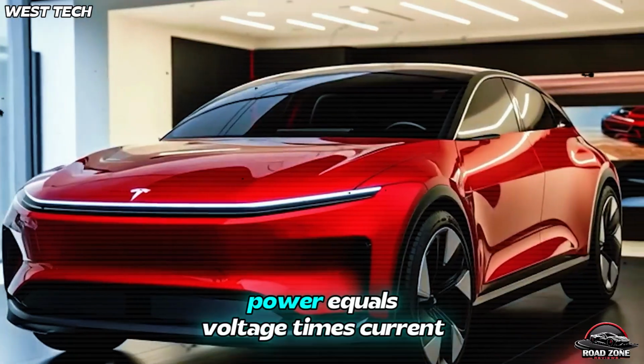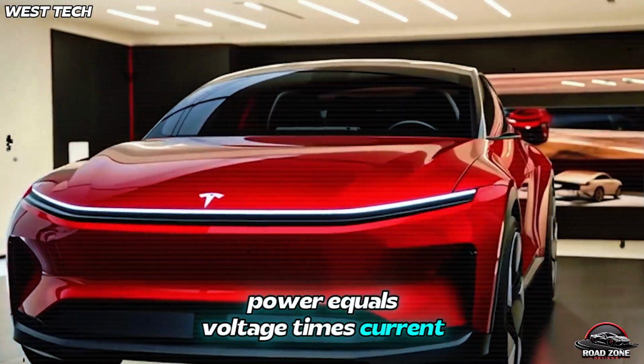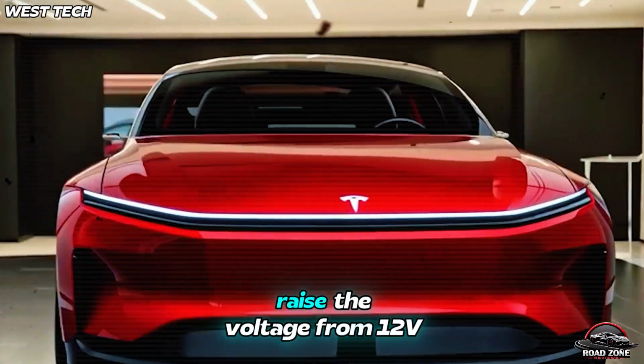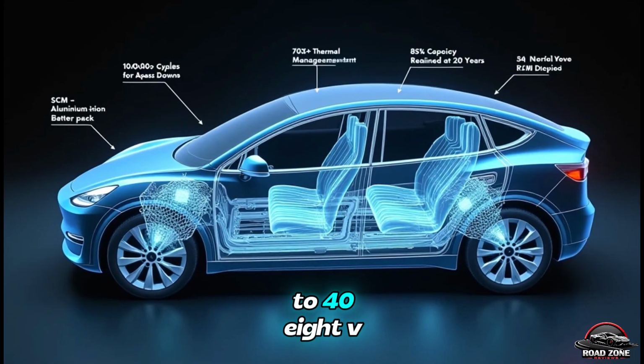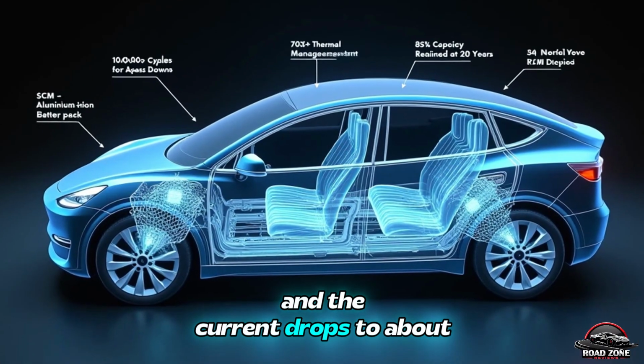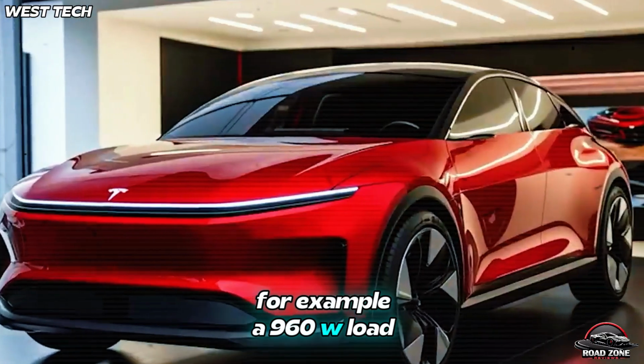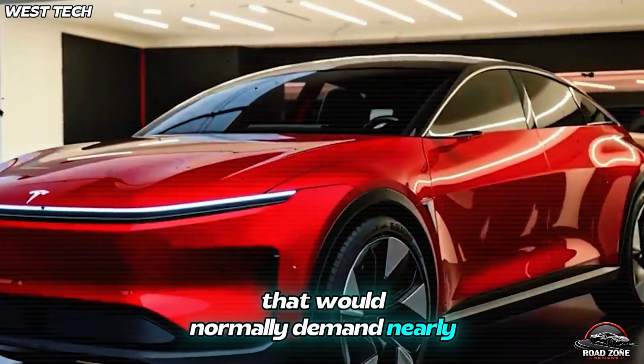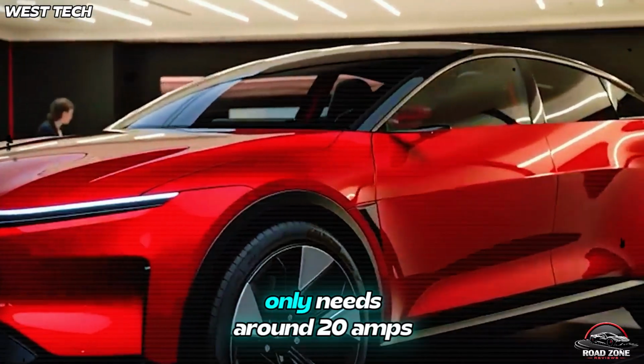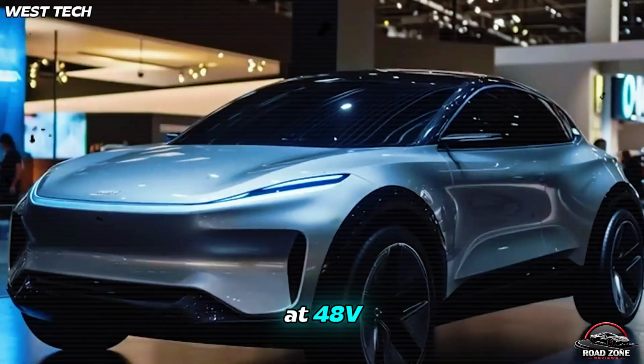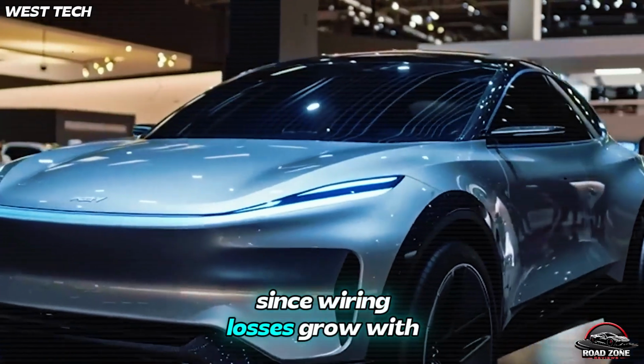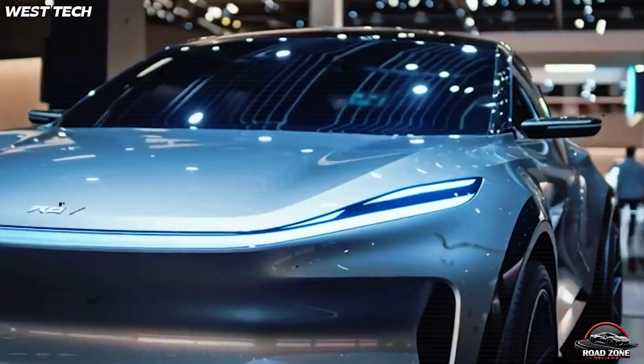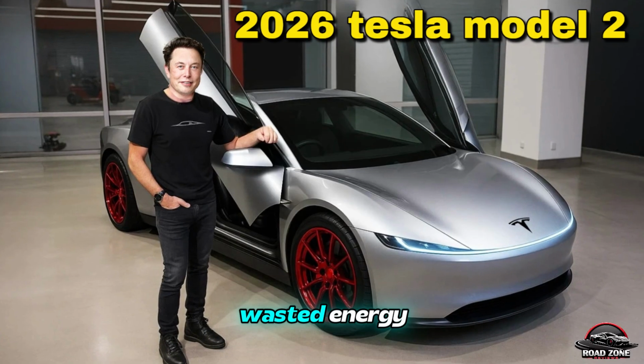The logic is simple. Power equals voltage times current. Keep the power constant, raise the voltage from 12V to 48V, and the current drops to about 1/4. For example, a 960W load that would normally demand nearly 80 amps at 12V only needs around 20 amps at 48V. Since wiring losses grow with the square of current, cutting current slashes heat and wasted energy.